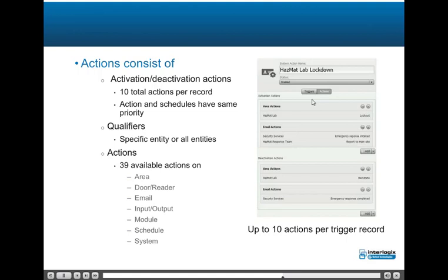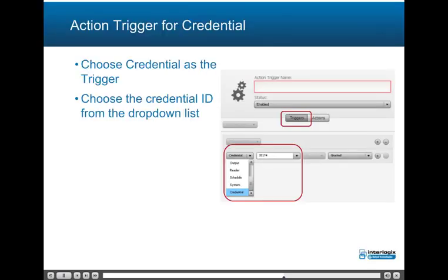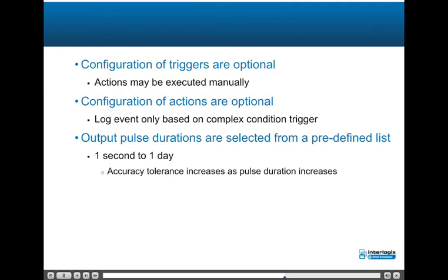Configuration of triggers is optional; actions may also be executed manually, and configuration of actions is optional. An option exists to log event only based on a complex condition trigger. Output pulse durations are selected from a pre-defined list from one second to one day; accuracy tolerance increases as pulse duration increases. Email notification action is processed FIFO when multiple actions occur; email text may be customized and is included on the first line of the email body. Retry limit controls delivery expiration relative to the time the action was triggered. Email notification events generated include: email successfully sent, email sent failed, all attempts failed, email sent expired (retry timed out prior to any delivery attempt), and email sent disabled (email notification is globally disabled).